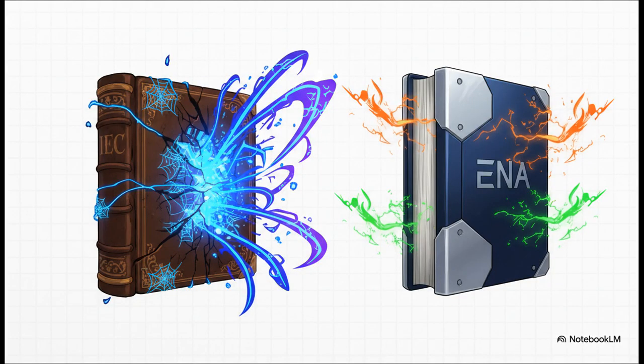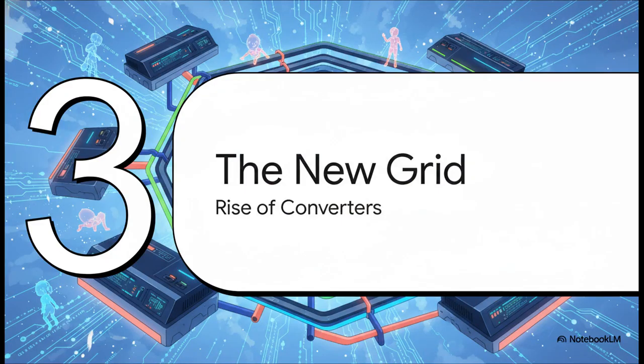But here's the catch. IEC 60909 is getting a bit long in the tooth. Its last big update was back in 2016, and the grid has changed a lot since then. And while the newer ENA G74 does try to account for what's called converter-fed generation, or CFG, it still doesn't quite nail the complex, dynamic way these new devices actually behave when a fault hits the system. And this gets us right to the heart of the problem.